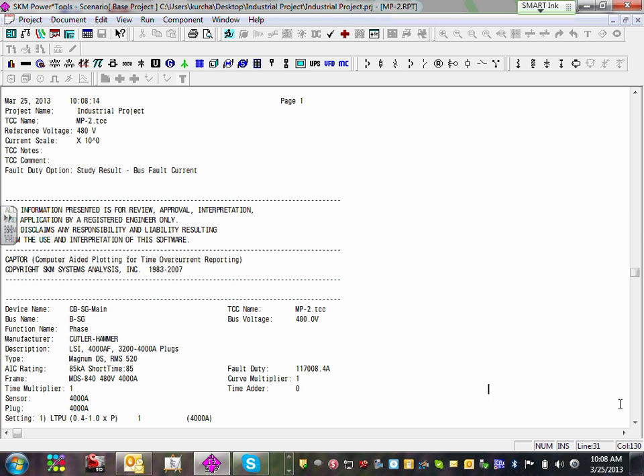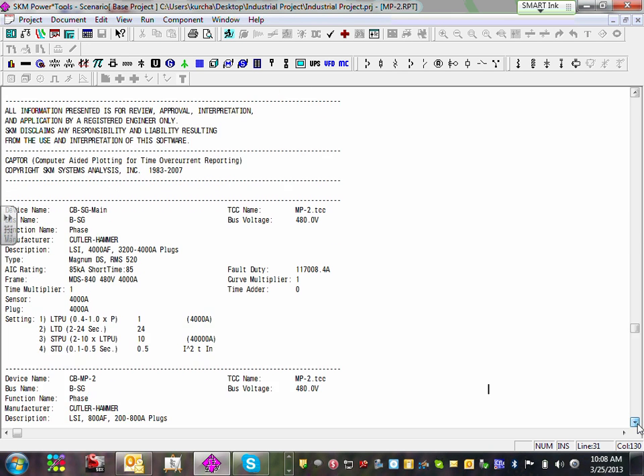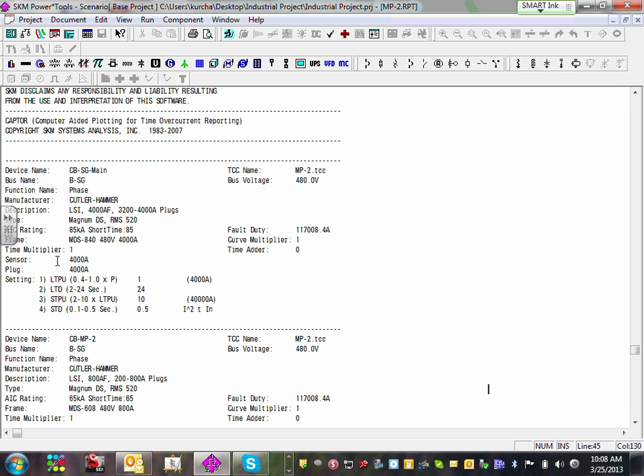When you look at the settings you've already done, can you guys see what the main is set up right now? Your main sensor is 4,000, the plug is 4,000, the long time pickup is 1, long time delay is 24, short time is 10, short time delay is 0.5. That's exactly what we were just talking about.